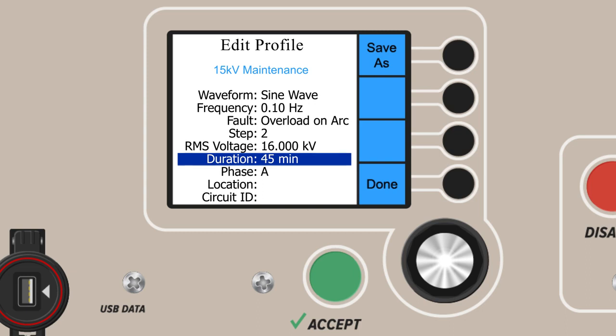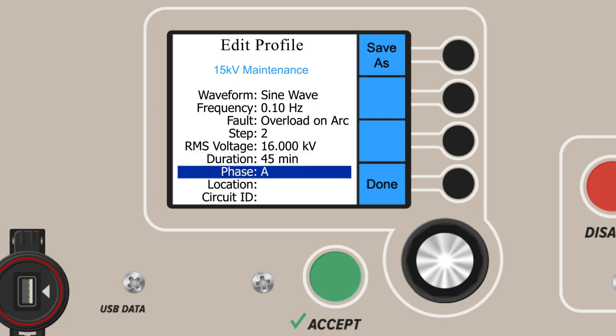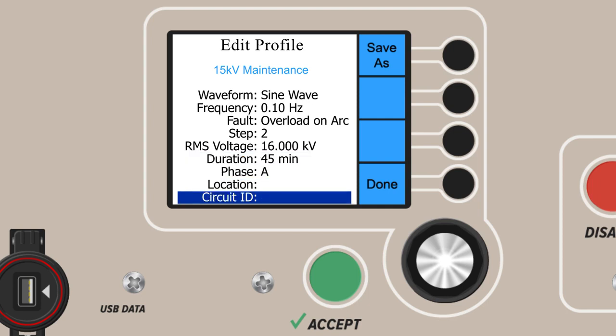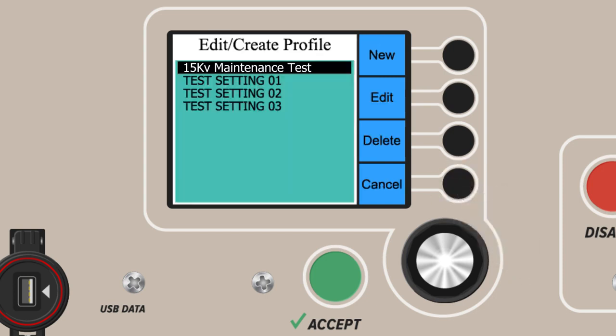The last fields on the test profile creation are optional. With phase, location, and circuit ID fields, users can identify the devices under test or sections of a workplace they were working within. When all the parameters and fields needed have been properly set, select the Done button. The test profile is now complete and saved. It will now be available under the Saved Test Setup section of the main menu.